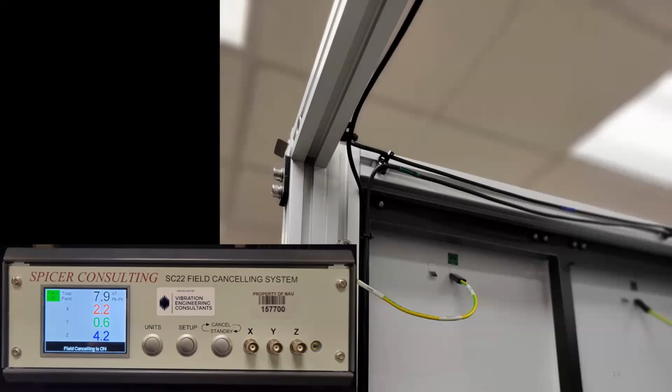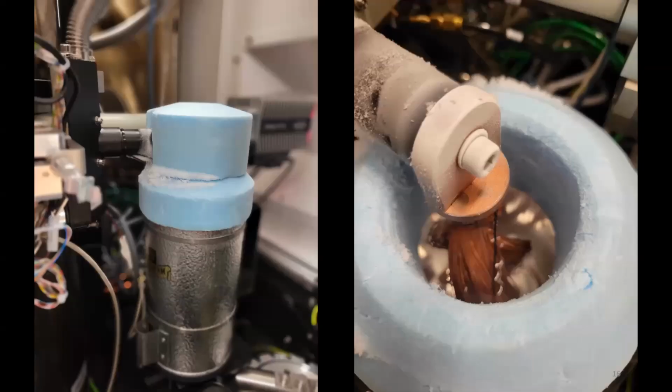Normally it would be about 30 to 40 nanotesla peak to peak, which by the way is actually okay for a TEM, but we can take it down to, this is on the high end, it goes between 4 to 8 peak to peak. In the Y direction, there's practically nothing. I think that's because there's the cabinet right behind it that's kind of blocking everything. And the reason is they gave us a room which is next to the magnetic resonance. Yeah, we're right next to the NMR lab, by the way.